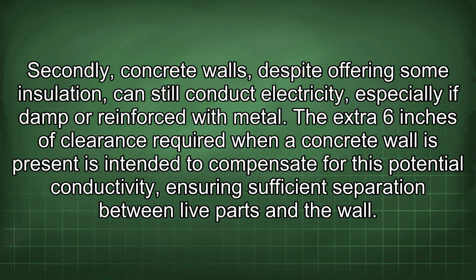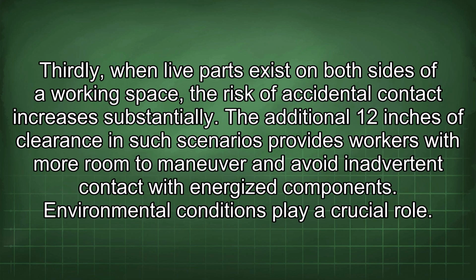Secondly, concrete walls, despite offering some insulation, can still conduct electricity, especially if damp or reinforced with metal. The extra 6 inches of clearance required when a concrete wall is present is intended to compensate for this potential conductivity, ensuring sufficient separation between live parts and the wall. Thirdly, when live parts exist on both sides of a working space, the risk of accidental contact increases substantially. The additional 12 inches of clearance in such scenarios provides workers with more room to maneuver and avoid inadvertent contact with energized components.